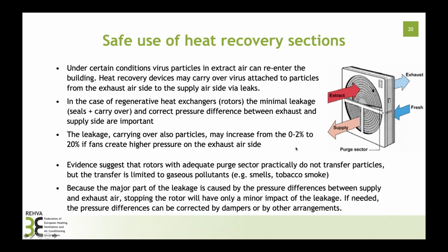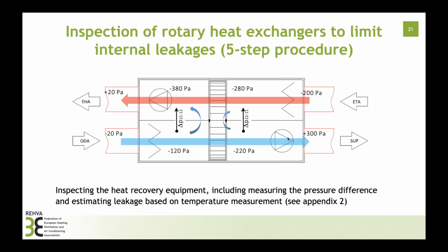And then it is important to know what the technical condition of such heat recovery equipment is, because leakage commonly should be less than 2%, but very easily can increase to 20% if pressures are not correct or seals are not in good order. So that's the reason we have developed together with Eurovent a five-step inspection procedure for rotary heat exchangers, and the recommendation is to conduct this inspection for all rotary heat exchangers if somebody suspects that these systems do not work correctly.